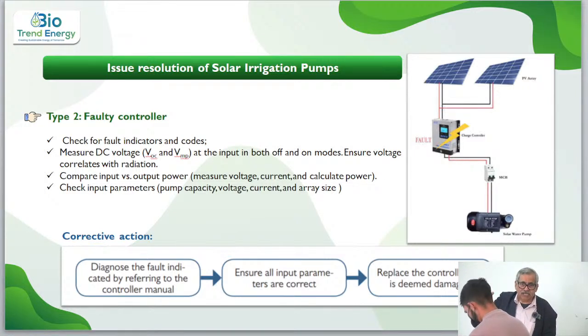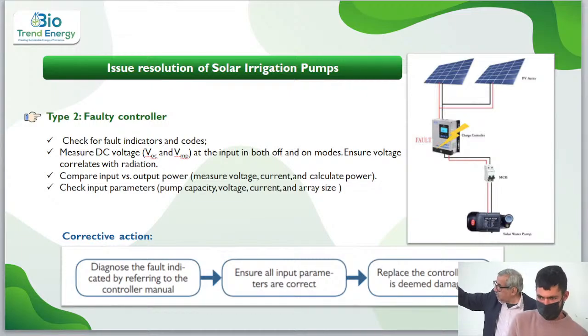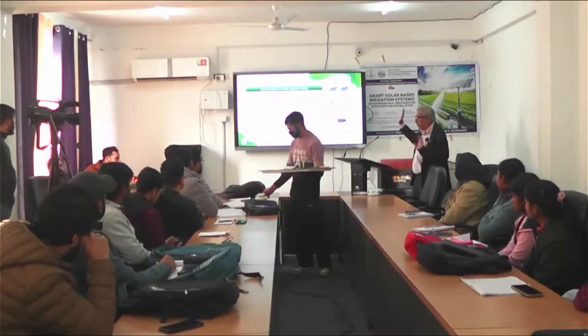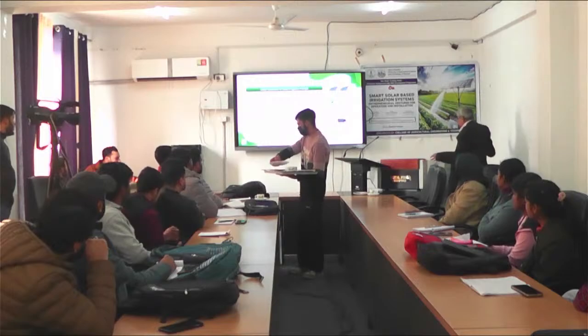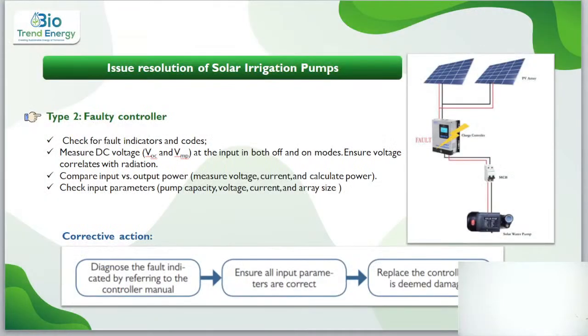So that is the second level of connection checking. One is the solar array, the PV array. I have checked that, and now the controller. Now assuming these two are okay, I will go to the third level. Very simple. Otherwise, it's only two or three components. But because these are in the field, in the open, with no control of the ambience, something can happen all the time.